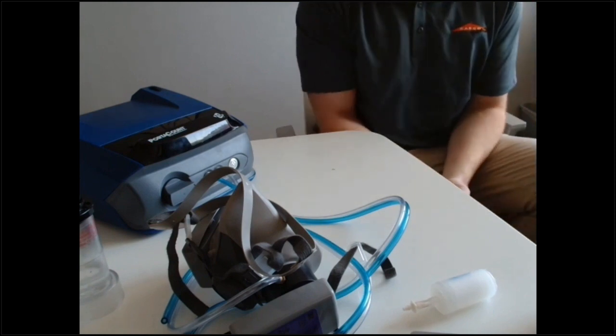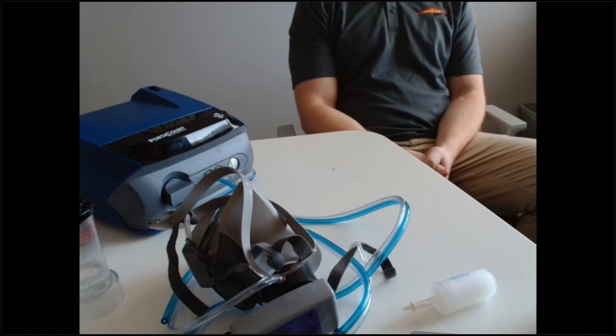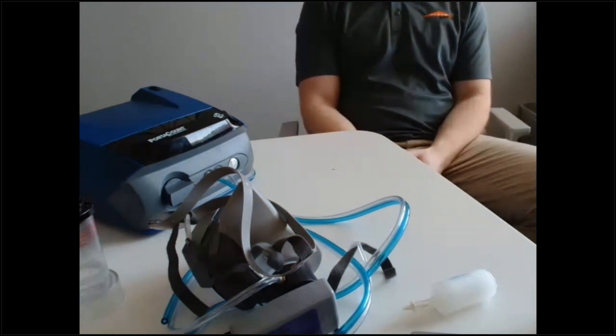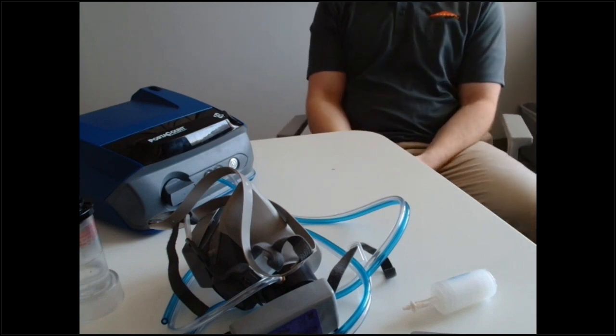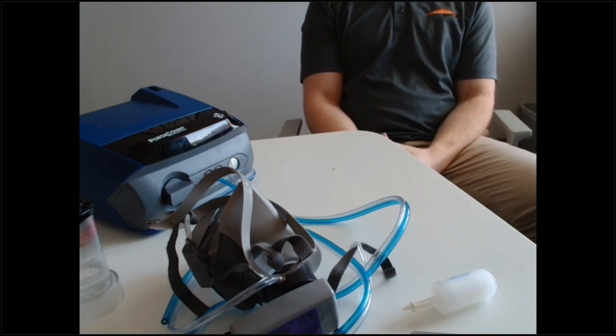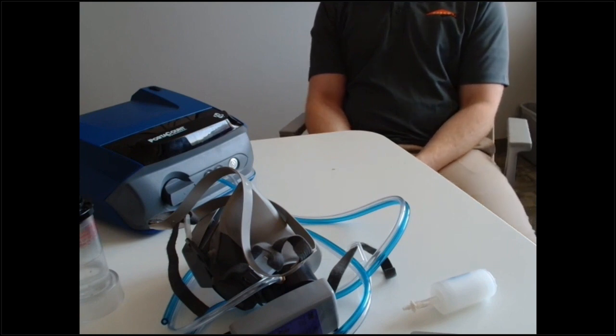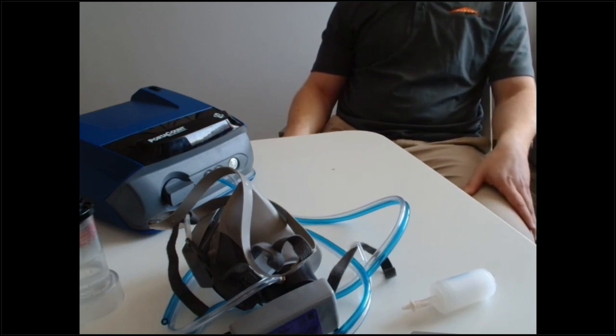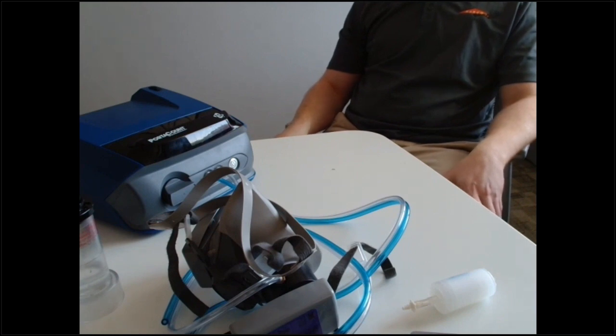Question: if you take a break for lunch, should you do a daily check again? You don't have to — the daily check is literally once per day. I would look at what particle level you had before the break. If you're doing full-face testing and had 5,100 particles in an enclosed room, you're probably okay. It never hurts to do another one, but it's not required. Typically during the day more particulate is generated as people move around, so if you were good in the morning you'll likely be fine later.